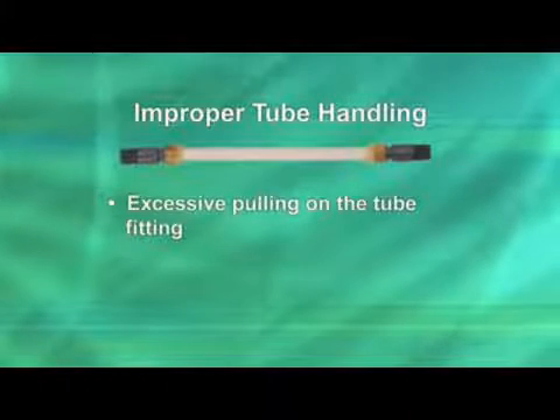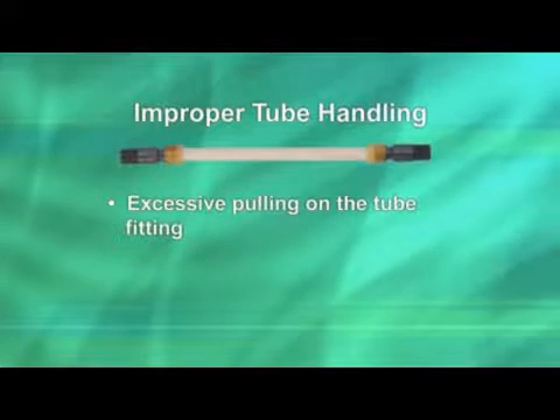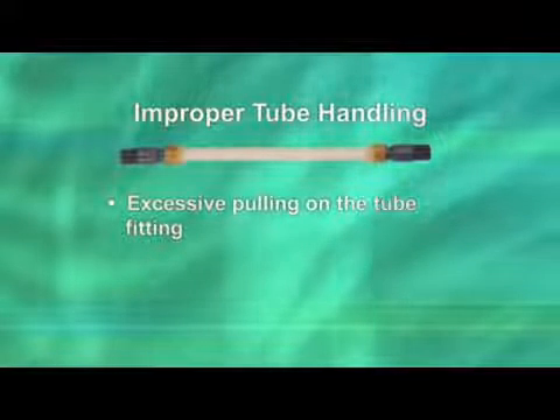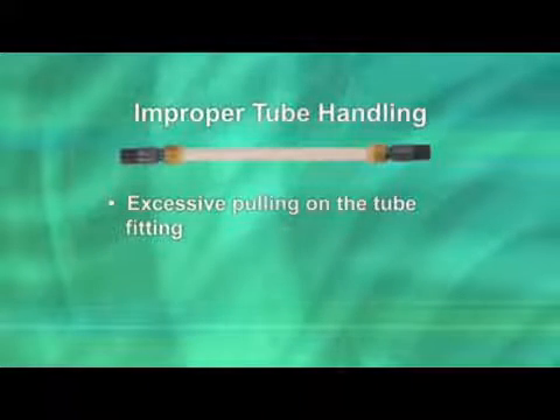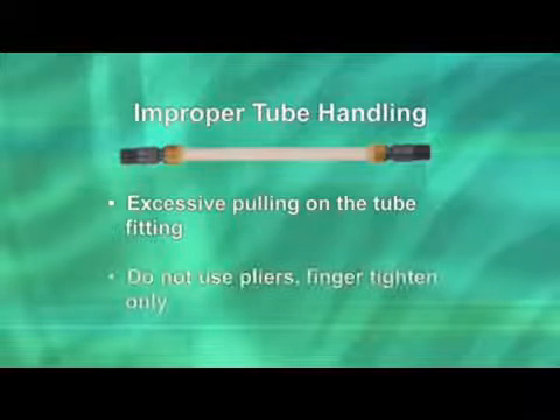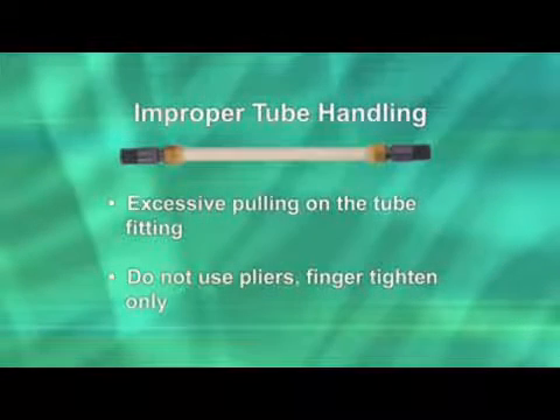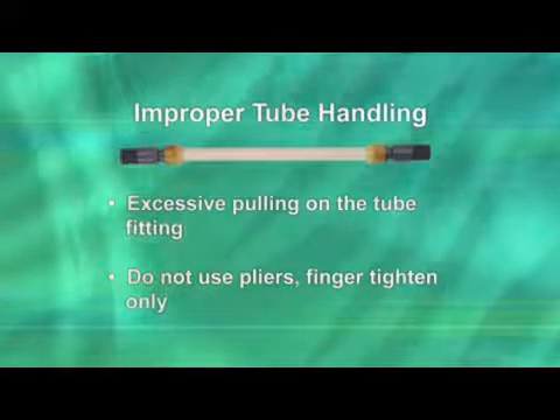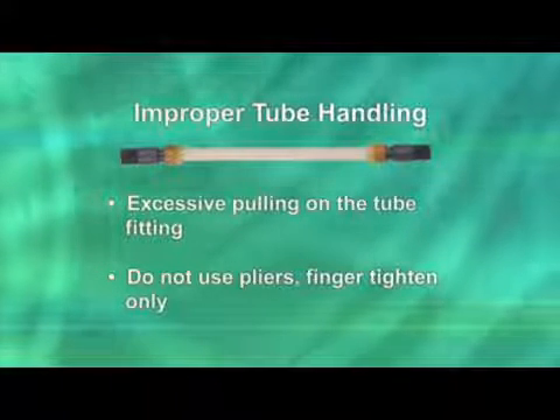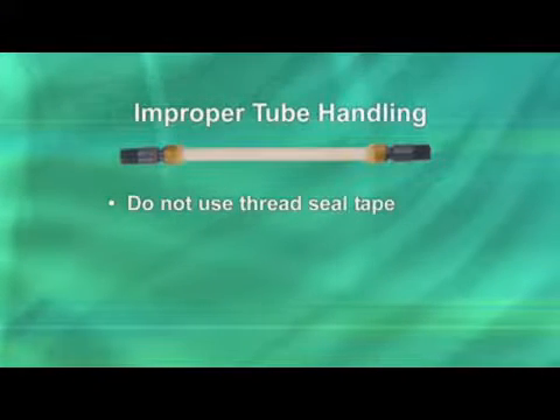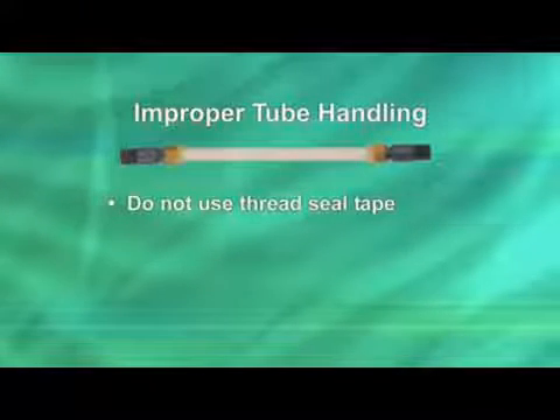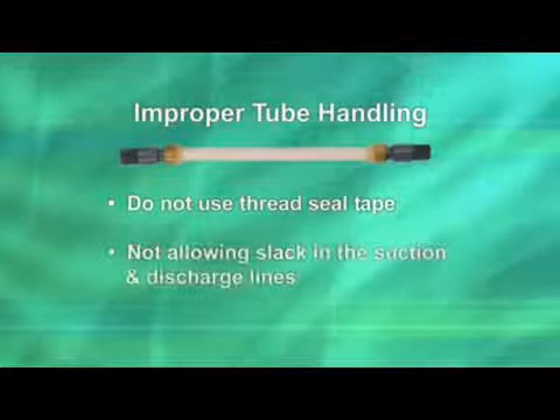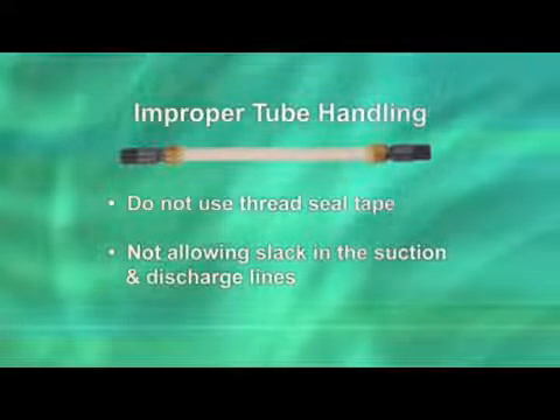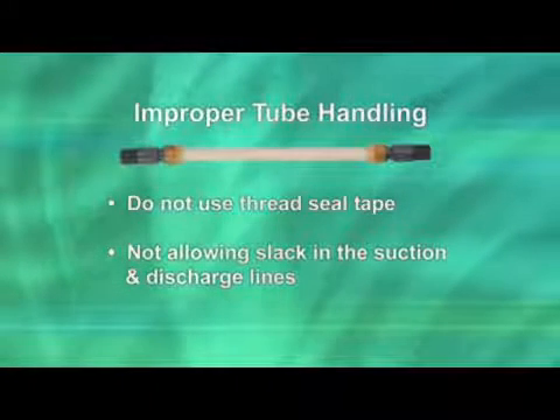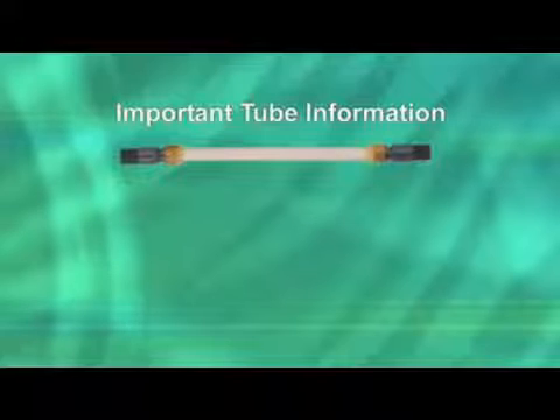Excessive pulling of the tube fitting during installation can result in compromising the material and/or pulling the crimped fitting from the tube. Allow the rollers to stretch the tube into position according to the tube replacement instructions. Using pliers to center or secure connections can break the internal crimped seal or damage ferrules due to over-tightening. Finger tight only. Using thread seal tape prevents ferrules from seating properly into the tube fitting and can cause leaks. Not allowing enough slack in the suction and discharge lines so the tube fittings can flex puts stress on the tube and fittings.